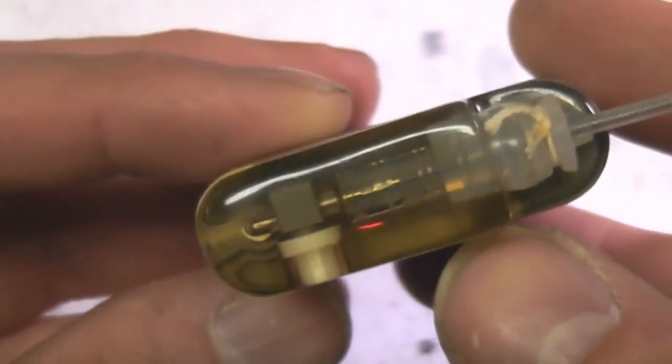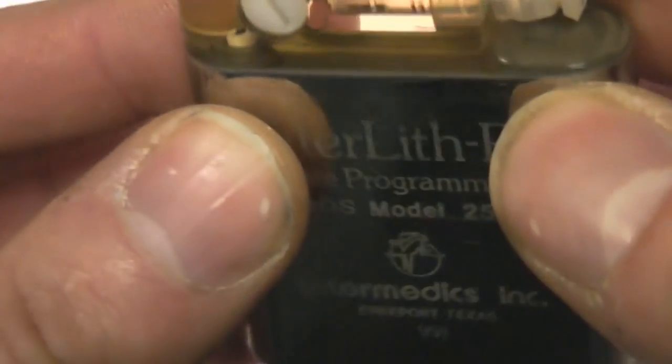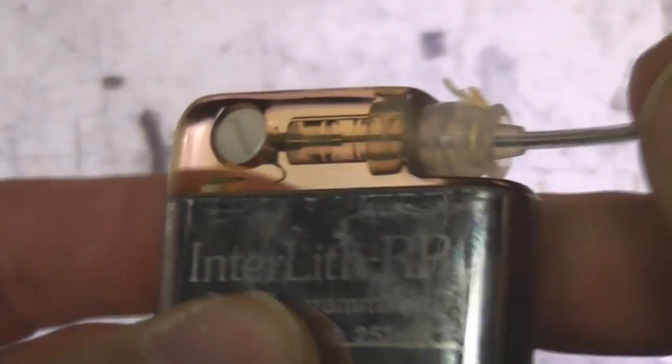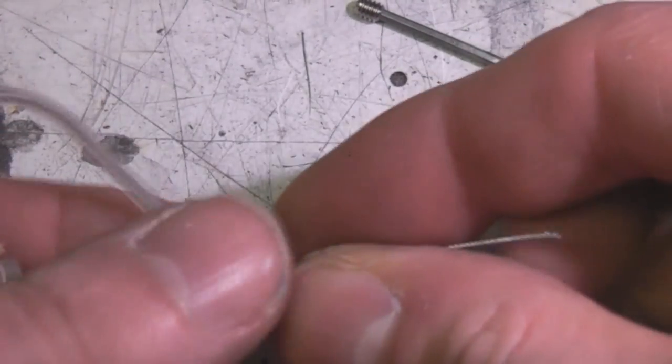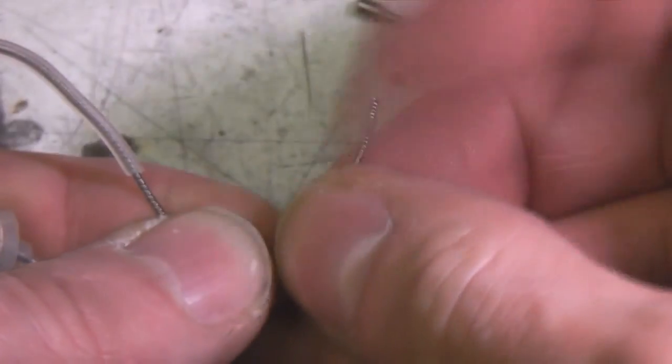The main enclosure is metal, I'm guessing probably titanium, and it appears to be welded. It's also got this clear resin part on top of the quite complicated connector. There's a screw here that comes out, and there's an Allen key in here. The cable that comes out has a silicone sleeve and the inner wire is springy, again presumably titanium.